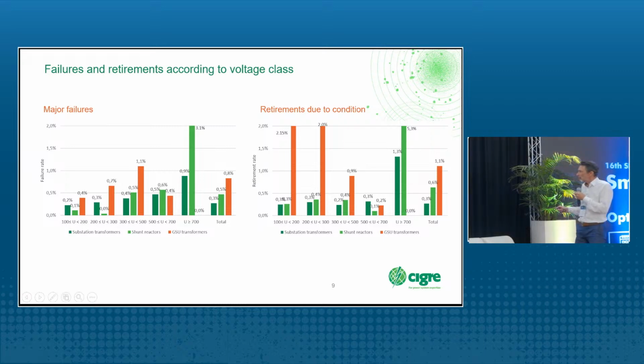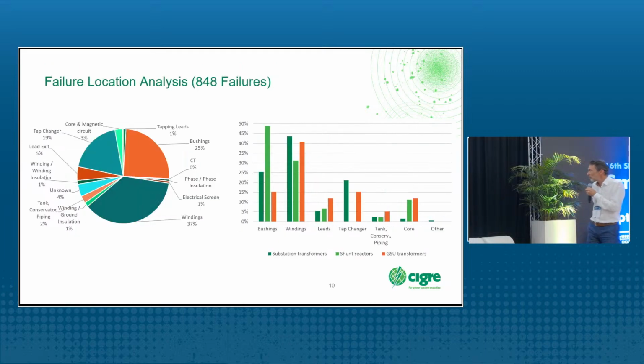Let's say the average failure rate here is 0.3%. What is the meaning of 0.3%? If you have a population of 300 transformers, it means one will fail in a year. So I would say the reliability is quite high. This is really a good value, I would say. On the other hand, we also investigated the retirements. The retirement rate is a little bit lower than the failure rate. I don't think that it is necessary to go too much into the details here.